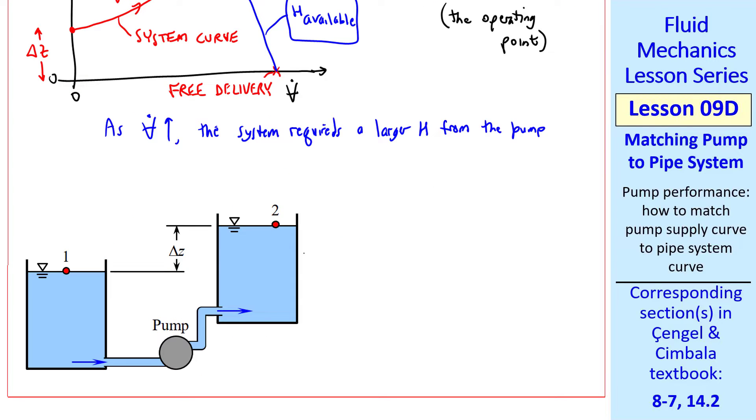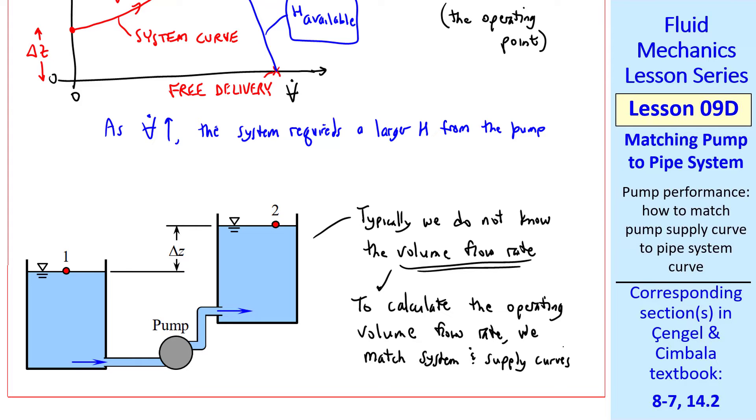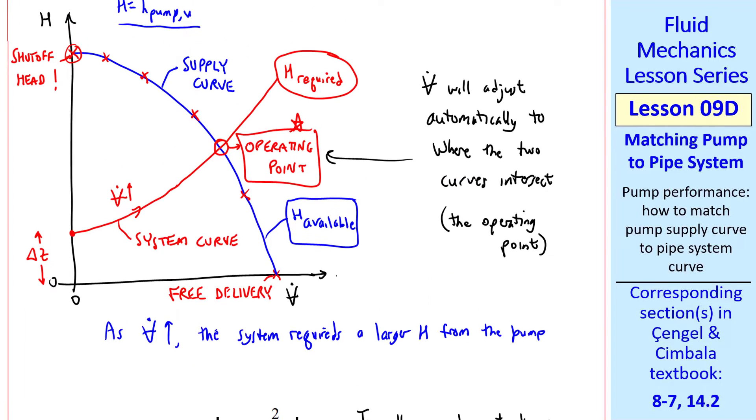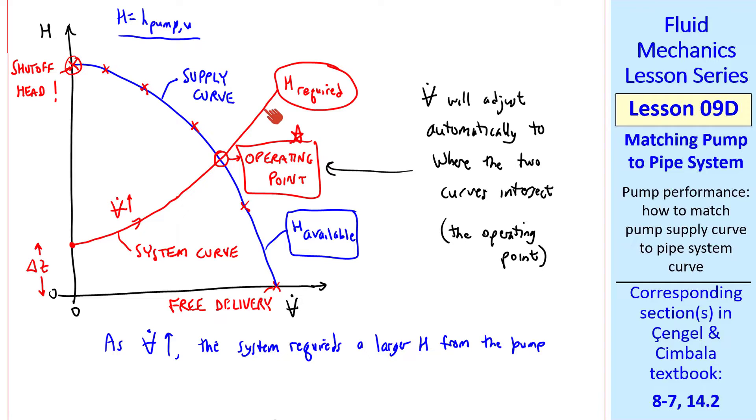In a flow system like this, typically we do not know the volume flow rate. This is our unknown. To calculate the operating volume flow rate, we match system and supply curves, like I illustrated here. Again, these curves meet at only one point and that will be our operating point at a certain V dot and at a certain head. I label this point the operating head and this point the operating volume flow rate at the operating point.